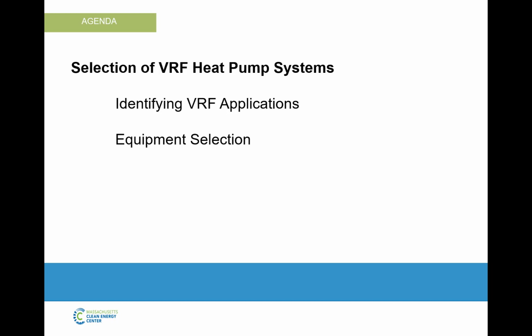The question was, do we have any data on life cycle cost comparisons between something like a 4-pipe chiller boiler system and a VRF system? Every one I've done and seen has always been project specific. Even if you look at just 4-pipe chiller boiler, the range of equipment can be wide: on the lower end an okay efficiency standard system, or a best-in-class chiller boiler system, which is going to be significantly different for life cycle costs. It's the same with VRF. You can have a very simple heat pump system or a heat recovery with ductless units type of system.